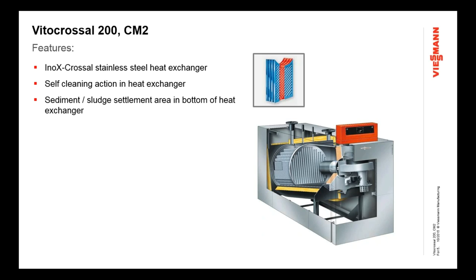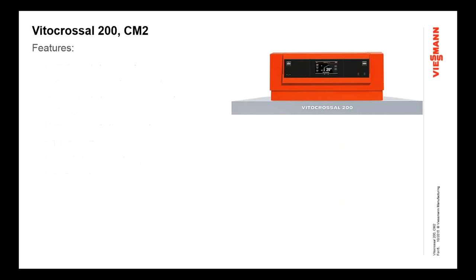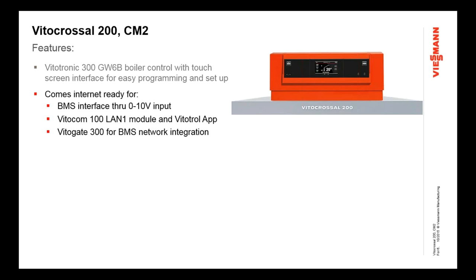Like all of our boilers for many years, it starts with a heat exchanger — the tried-and-true InoX-Crossal stainless steel heat exchanger. It provides a great feature of self-cleaning action and a sludge and debris sediment area in the bottom. The second part of that triangle is the burner — our own matrix cylinder pre-mix burner with high turndown rate, low emissions, and high altitude operation. The third part is the Vitotronic 300 GW6B boiler control, uniquely designed for this product, with a touchscreen interface and integrated cascade capability.